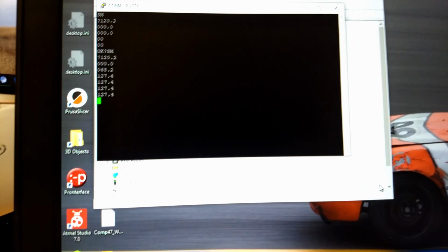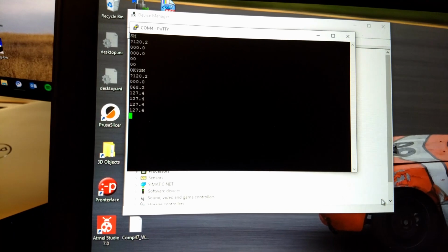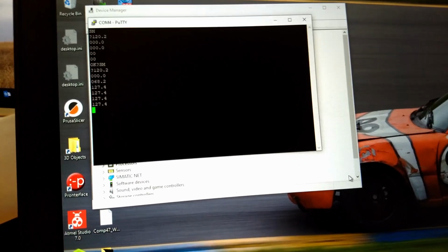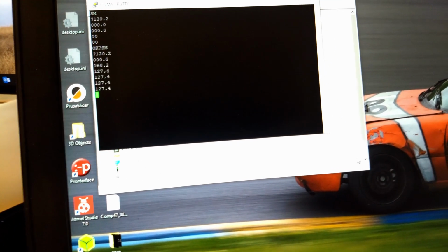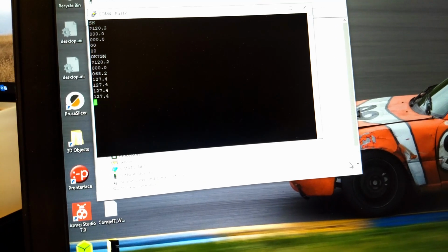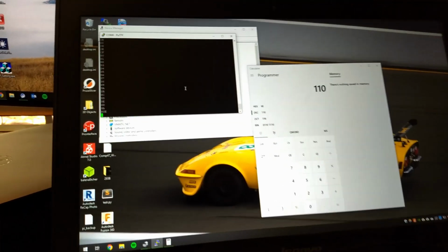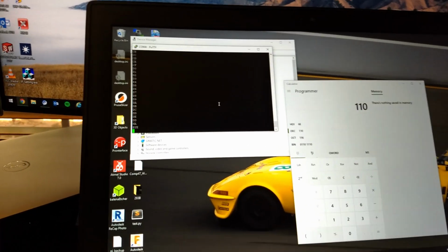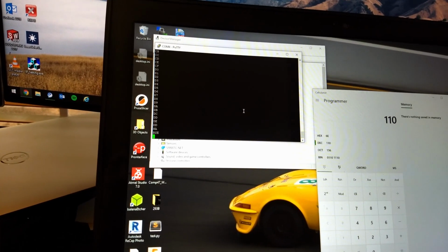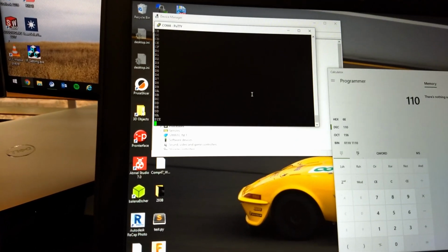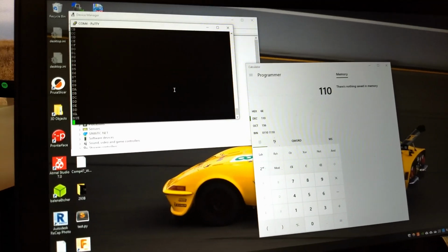We'd be hearing an alarm or the front panel would be going off if it was hooked up, but it's not. So now we'll go ahead and modify the value and show that this load is being reported as a smaller load and won't be tripping any alarms. All right. So what I'll show you now is, if you remember, we were getting 127% on setting two for the heat gun, and about 66, 67, 68% on setting one for the heat gun.